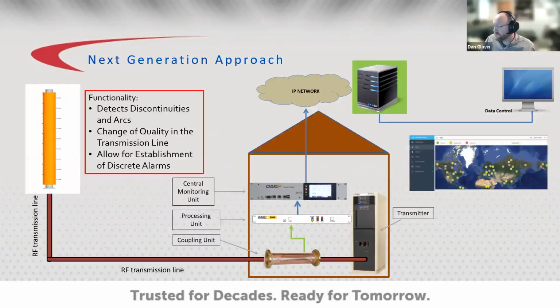So the next generation of real-time monitoring system is to implement a system that can be retrofitted into existing sites. The RFHawkeye has the ability to detect and localize arcs due to changes in transmission line integrity. It will characterize a system over time. It will also allow for discrete alarms to be established by the user based on known component characteristics. This system consists of a coupling unit sensor, a power meter, and a central monitoring unit.